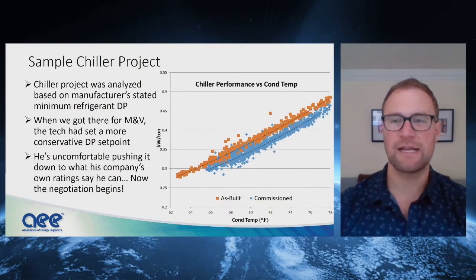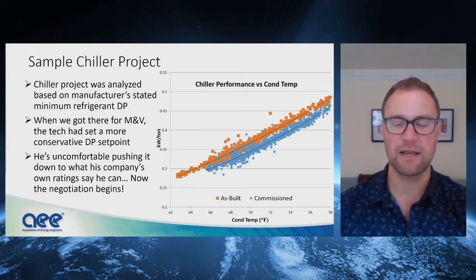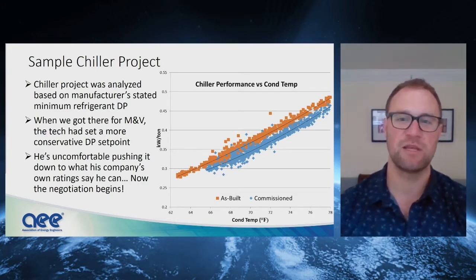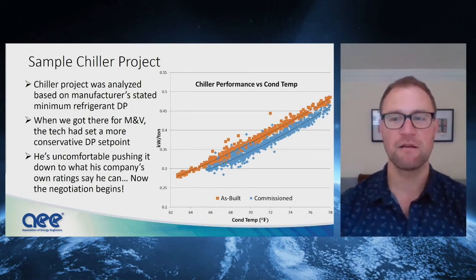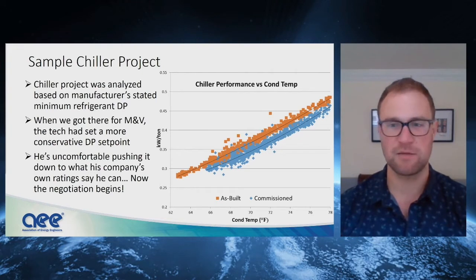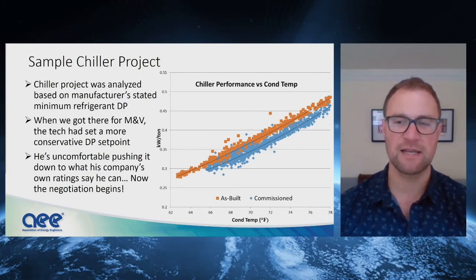So let's get into some real world data here to illustrate my point. This is a chiller project where we just weren't really happy with how the equipment was initially set up upon install. So we had to work with the field technician and challenge his assumptions a little bit. The project was studied and analyzed based on the manufacturer's stated minimum refrigerant differential pressure, DP. When we got there for M&V, they were following our recommendation to control based on DP, which is great, but the technician had set a much higher and therefore more conservative DP set point than what the manufacturer had indicated was possible. And that was used in the energy study.